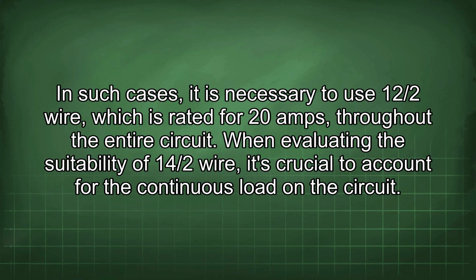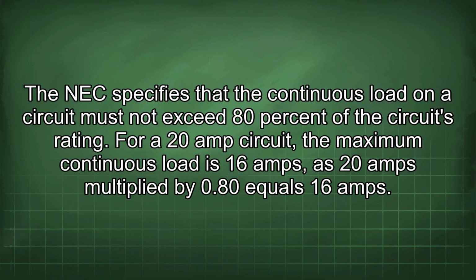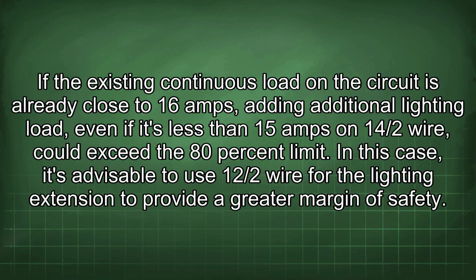When evaluating the suitability of 14/2 wire, it's crucial to account for the continuous load in the circuit. The NEC specifies that the continuous load on a circuit must not exceed 80% of the circuit's rating. For a 20-amp circuit, the maximum continuous load is 16 amps, as 20 amps multiplied by 0.80 equals 16 amps. If the existing continuous load in the circuit is already close to 16 amps, adding additional lighting load, even if it's less than 15 amps on 14/2 wire, could exceed the 80% limit. In this case, it's advisable to use 12/2 wire for the lighting extension to provide a greater margin of safety.